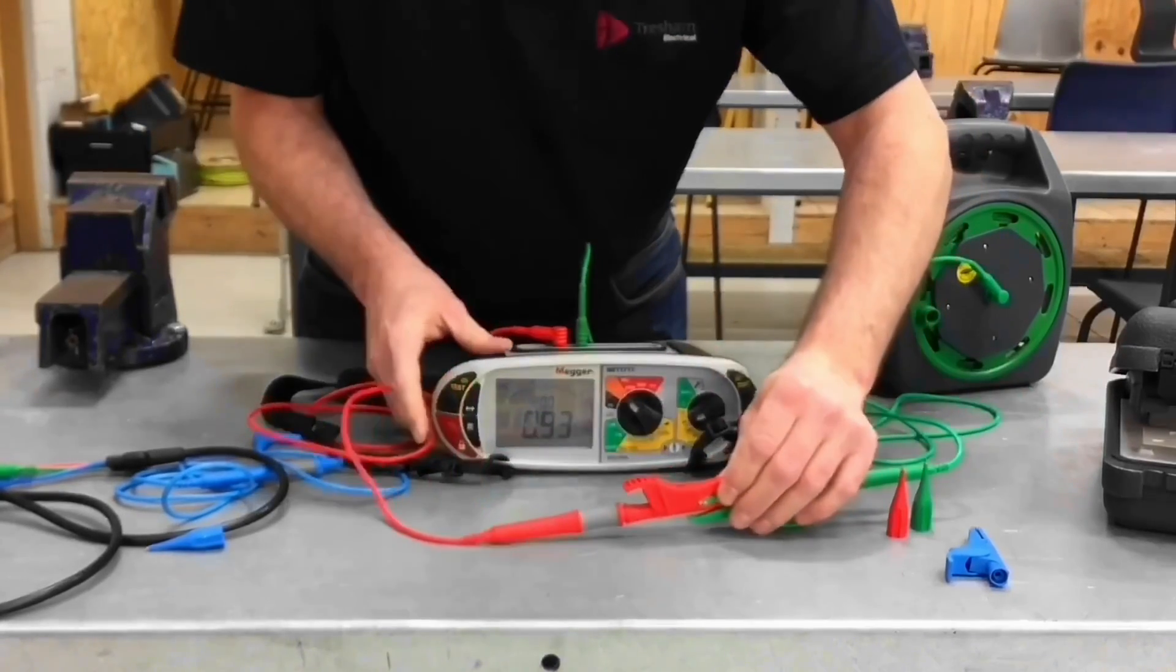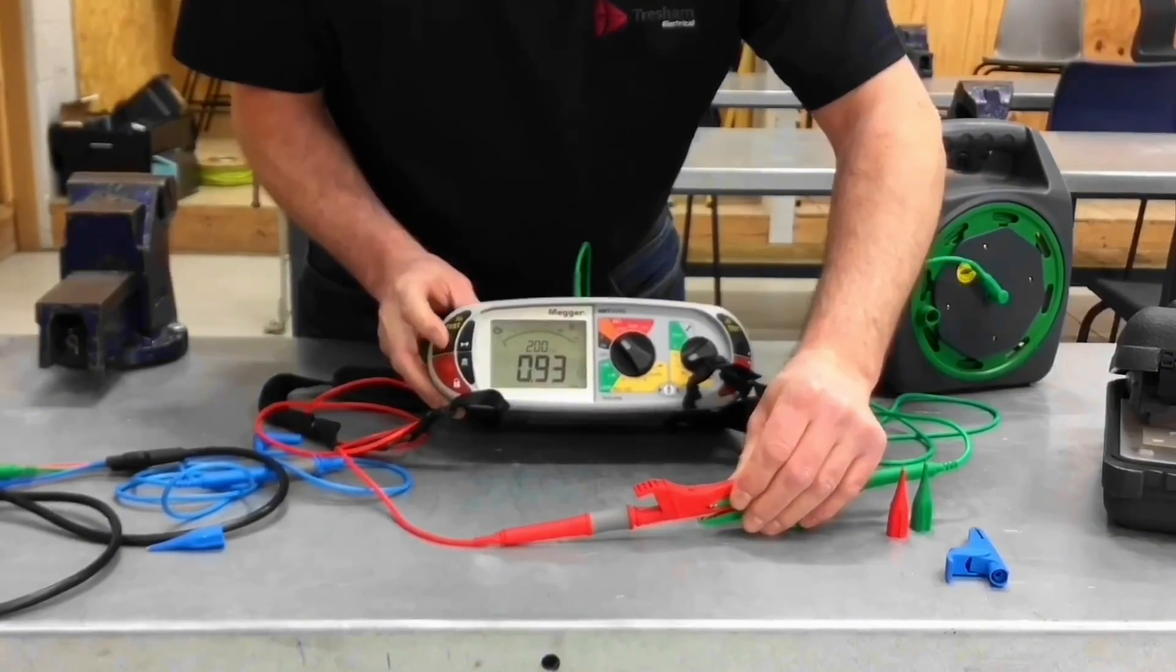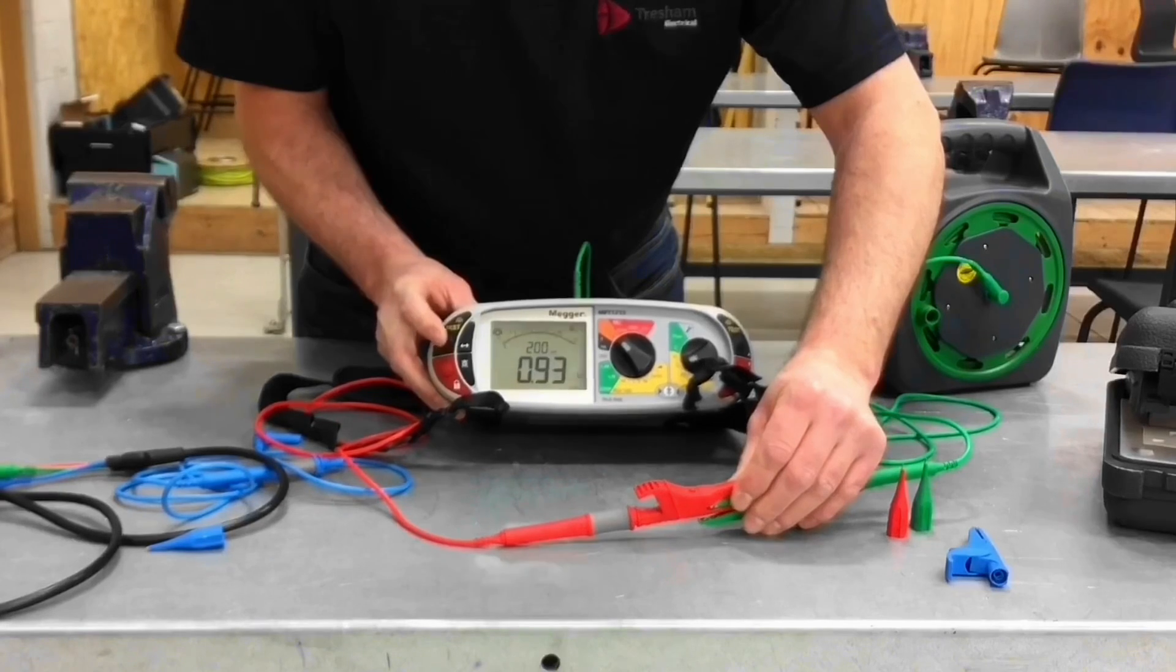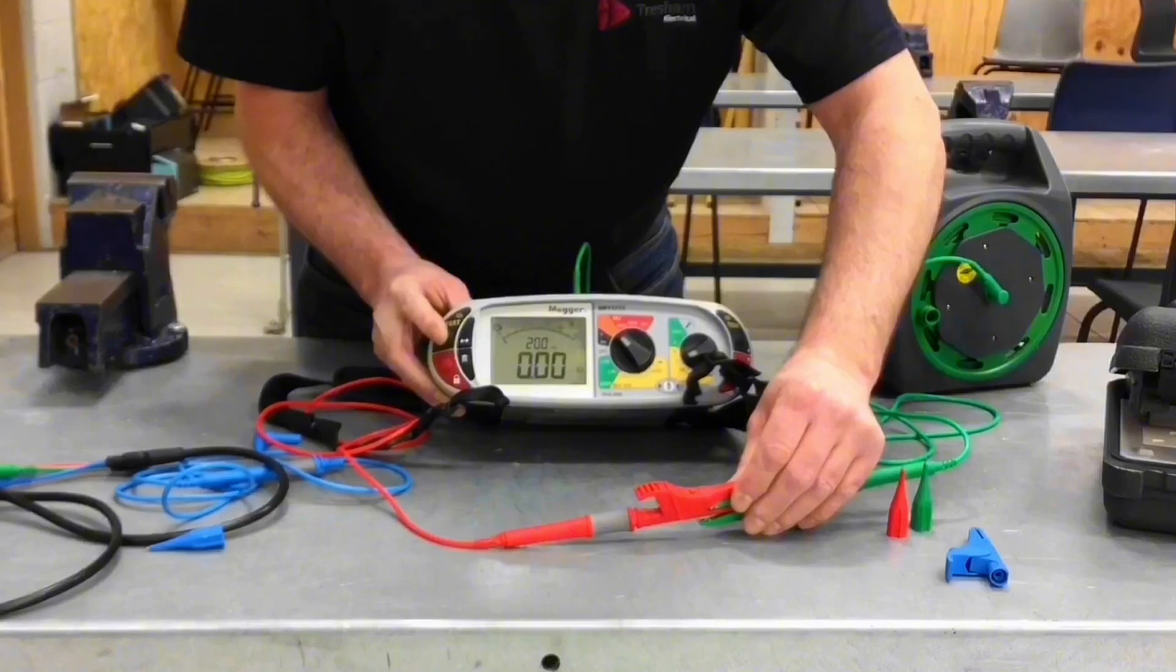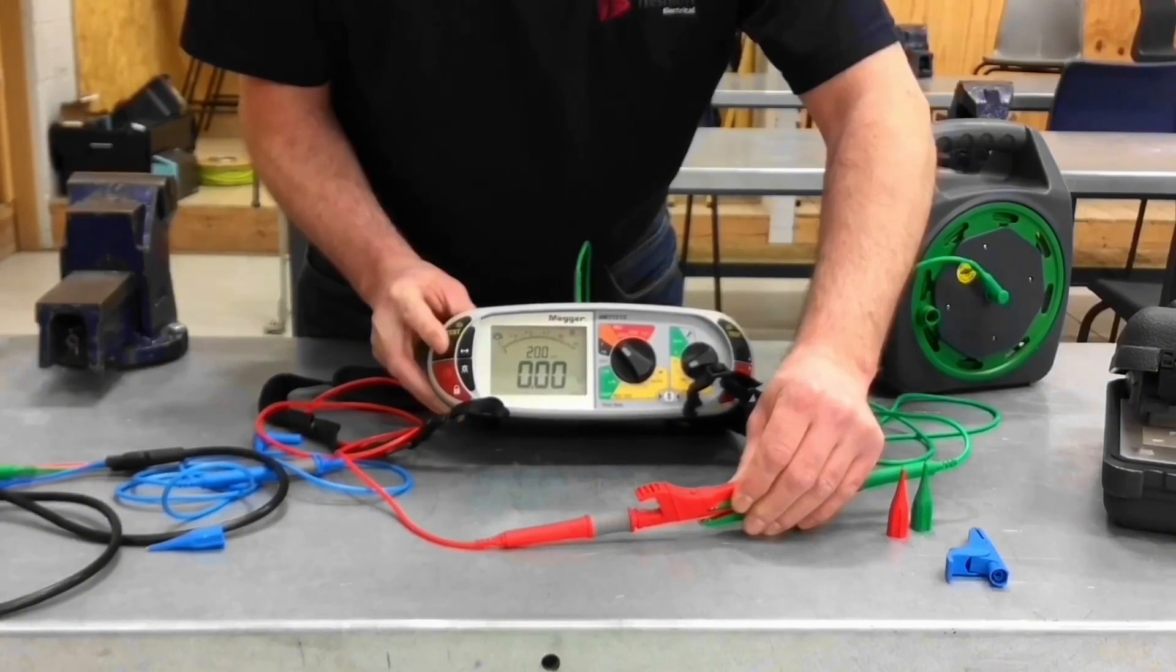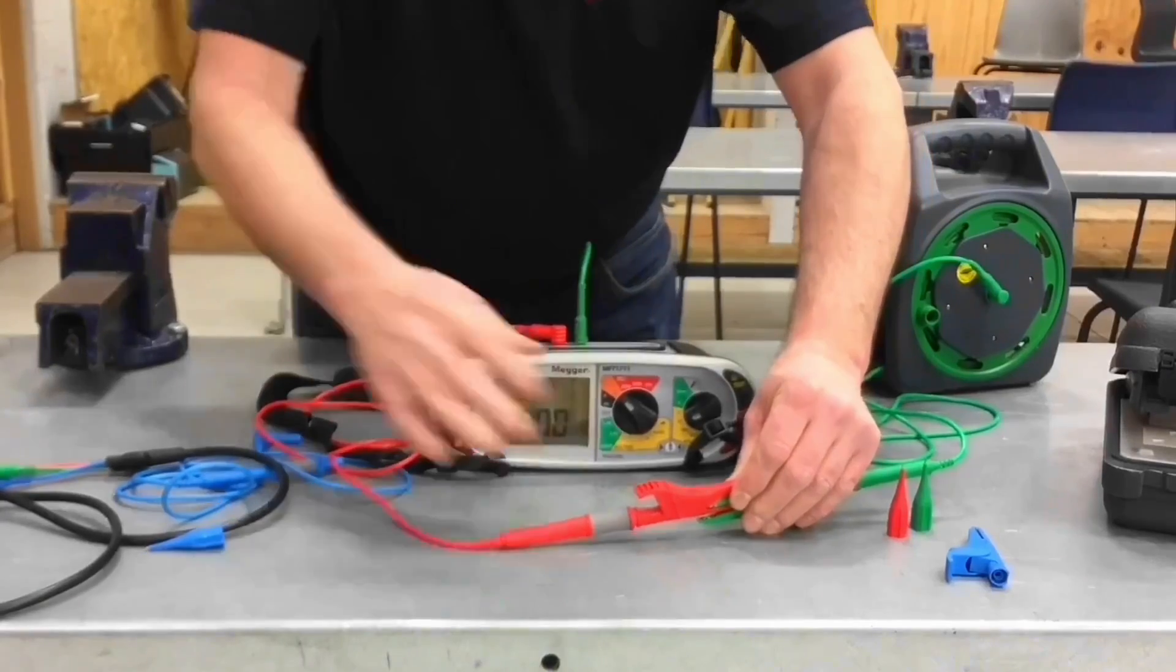A little squeeze, and we see we've got a reading this time of 0.93. Press the test button once. Press the test button again. So this time we've now gone down to 0. So I've zeroed out that 50 meter long lead, allowing me to go off to do R2 testing.